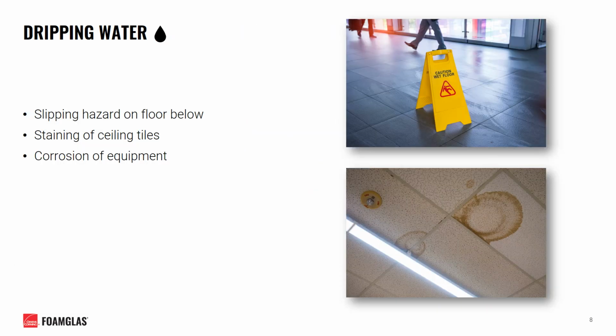In many cases, the most immediately noticeable symptom of a failed insulation system on a chilled water line may in fact just be the presence of dripping water from the system itself. If water vapor is allowed to penetrate the vapor barrier of the insulation and condense on that cold pipe, it can build up to the point where it then re-escapes the insulation and drips down below to whatever happens to be underneath. If that's a floor, it then poses a slipping hazard for any nearby personnel.